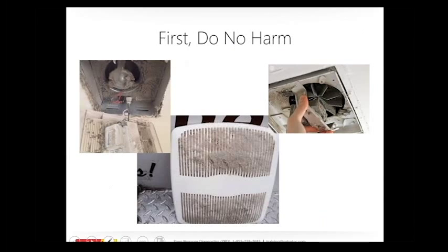These are pictures of bathroom exhaust fans and how dirty they've become. So what does that have to do with zone pressure diagnostics? Well, the way that exhaust ventilation works is that it's actually manipulating the pressure in the building or in the room to bring in fresh air. Now that's the problem, and so we say first do no harm in weatherization, right, Bill? Correct. But unfortunately, if you don't use ZPDs, or if you're not doing a very good job of air sealing, you might be sucking air that's supposed to be fresh air.